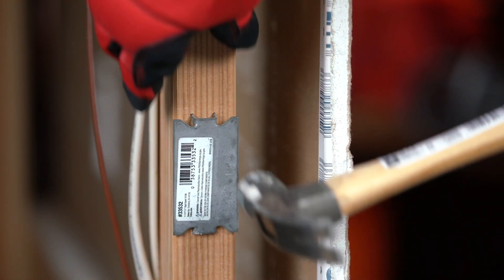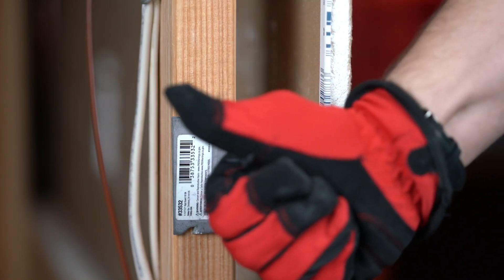If you have no choice but to drill near the edge, then you have to install nail plates on these studs to protect the wires from being penetrated by a drywall screw. There are a couple different kinds of nail plates, but they all just get pounded on by a hammer.